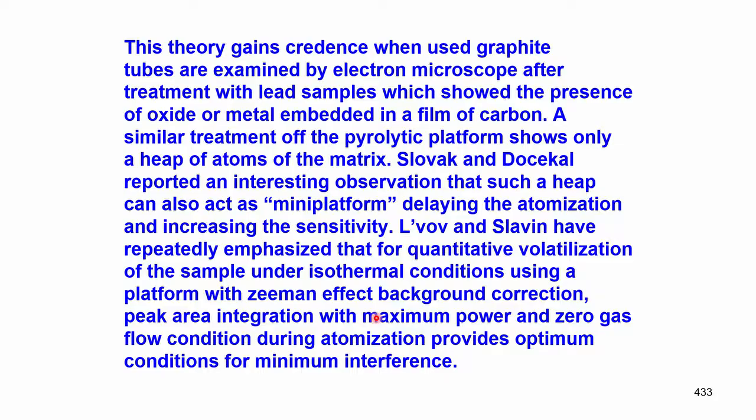So, the Zeeman effect, background correction, peak area integration with maximum power, zero gas flow condition, and during the atomization and the cleanup step, they provide the optimum conditions for minimum interference from other elements.